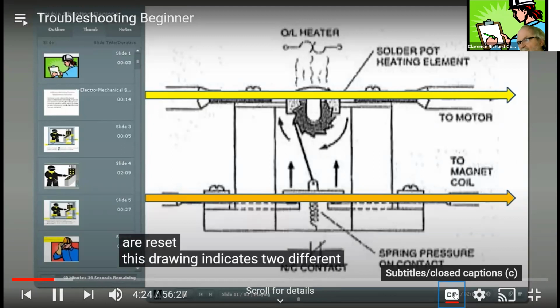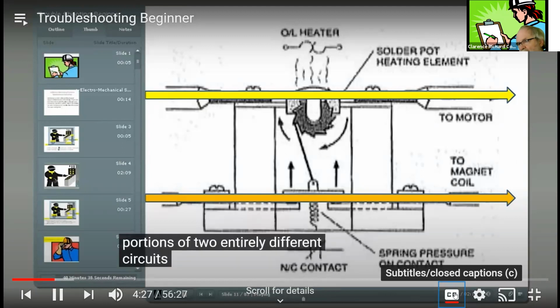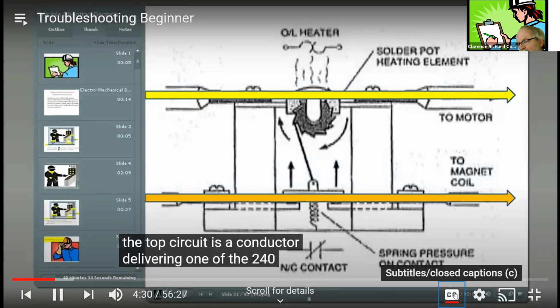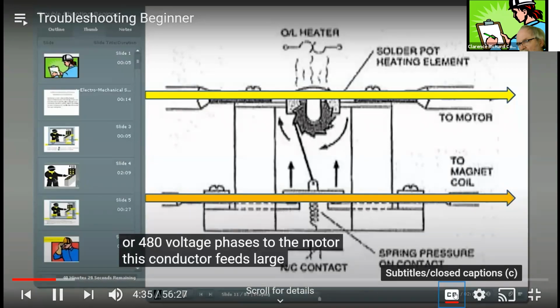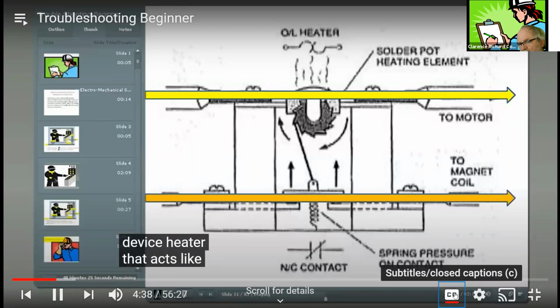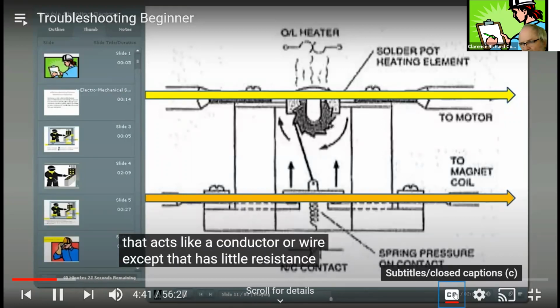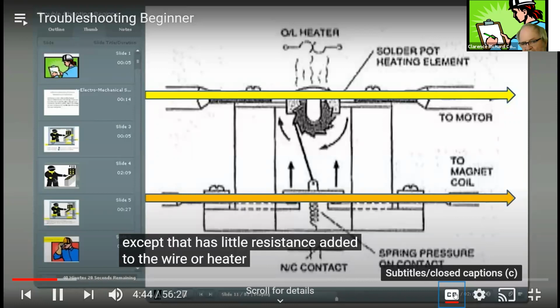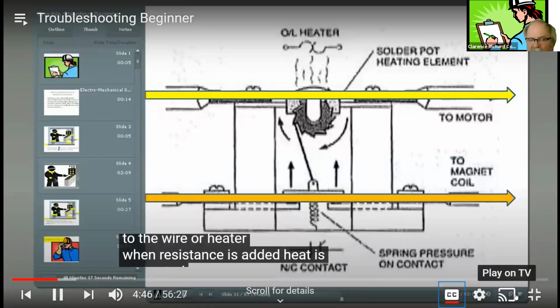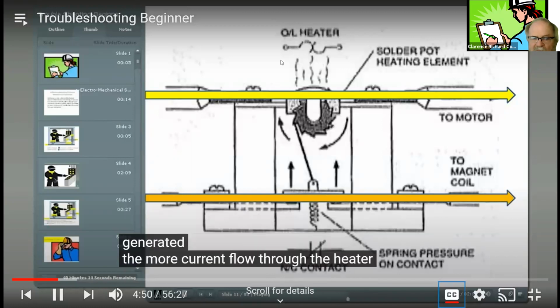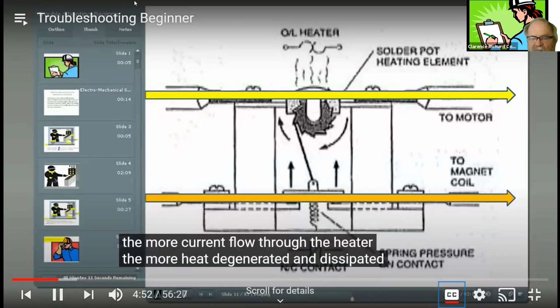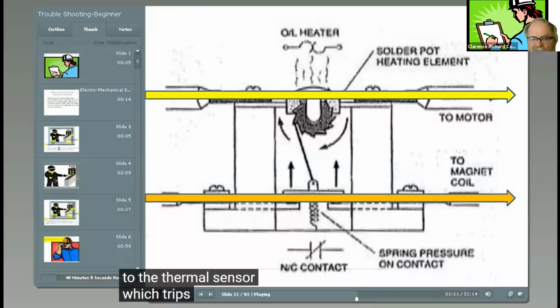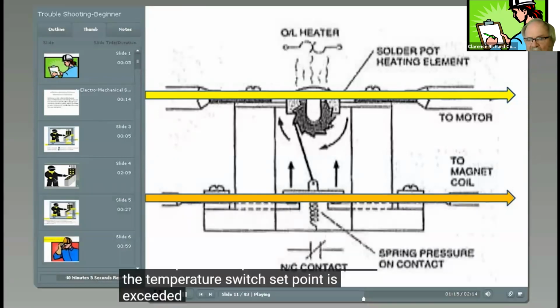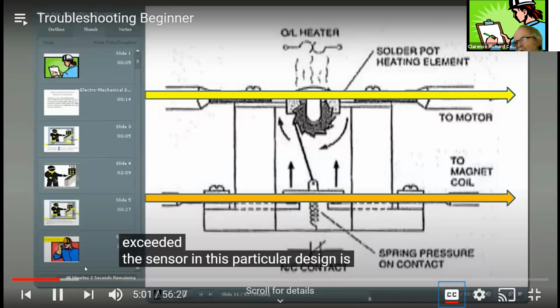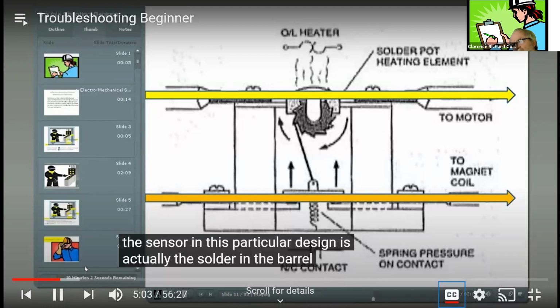This drawing indicates 2 different portions of 2 entirely different circuits. The top circuit is a conductor delivering one of the 240 or 480 voltage phases to the motor. This conductor feeds large wires to the device, the heater, that acts like a conductor or wire, except that it has a little resistance added to the wire. When resistance is added, heat is generated. The more current flows through the heater, the more heat is generated and dissipated to the thermal sensor, which trips the temperature switch when the set point is exceeded. The sensor in this particular design is actually the solder in the barrel that supports the axle of the ratchet wheel.